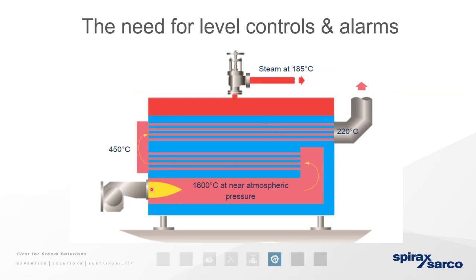So you have your burner coming on, and there will be a purge cycle as it heats up. Then the flue gases make their way through the passes and out the chimney. Steam here is being supplied at 185 degrees. And these boilers can have anywhere between 1 and 4 passes, so this can go 1, 2, 3, 4 times.